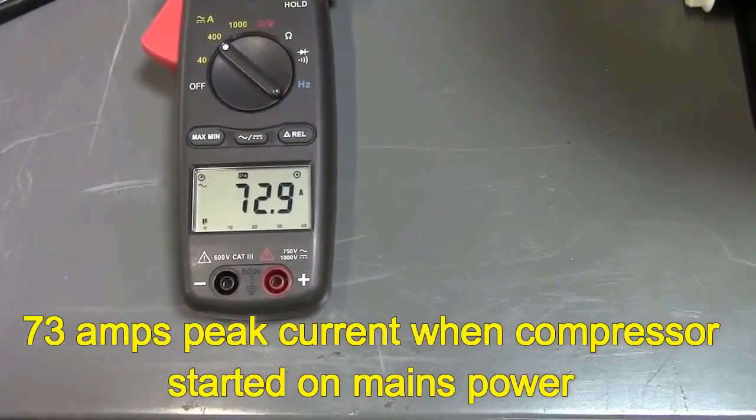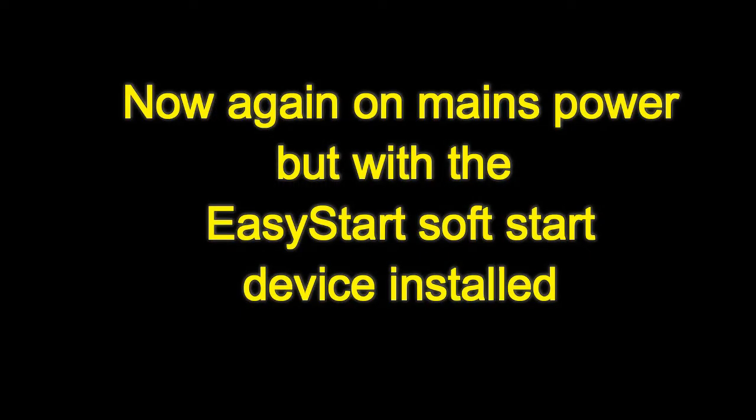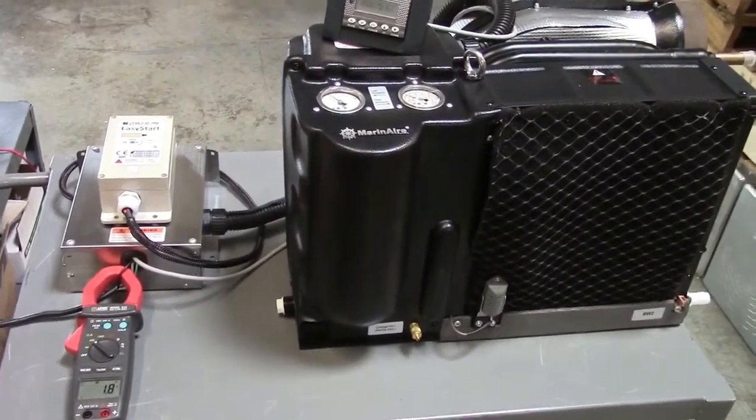It's going to be a lot higher than that once it gets going. When the compressor starts, we get 72.9 amps, so 73 amps.